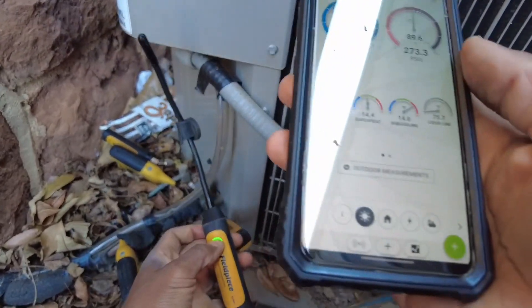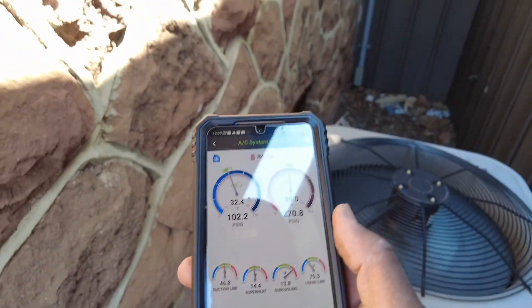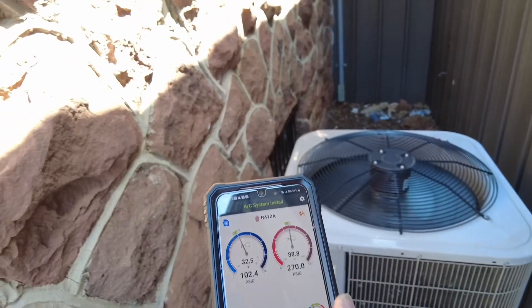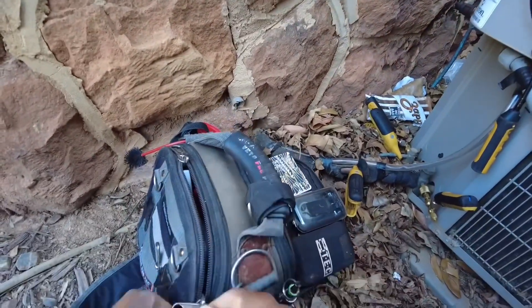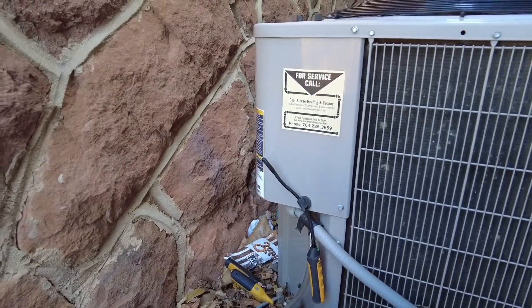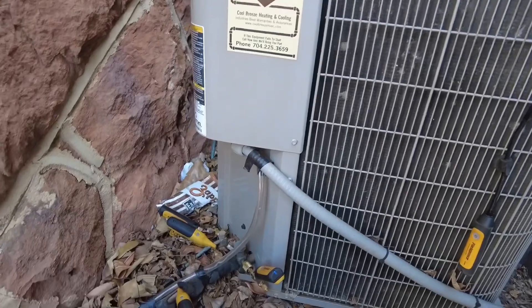Outdoor probe, as usual. I really do enjoy running an outdoor psychrometer — it helps out a lot. So far the pressures look pretty decent; it was pretty much just that filter as far as I'm concerned. I'm going to let it run because it's only been running for about five minutes now. While I'm letting this stabilize, I'm going to go ahead and check my volts and amps and things and check my power factor, which is an indicator of capacitor health.